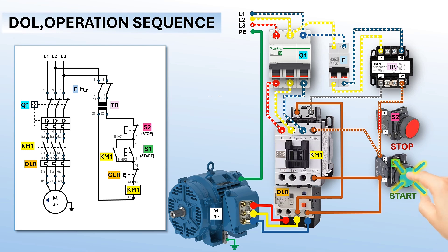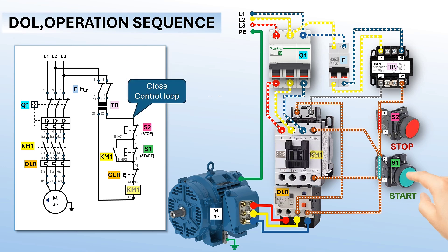To run the motor, press the start push button. Once the push button is pressed, the NO contact will close. Voltage at terminal 3 will directly pass terminal 4, then to overload relay terminal 96, and into terminal 14 of the auxiliary contact. From the overload relay NC contact terminals 95 and 96, the voltage will pass and reach terminal A1 of the contactor coil. When the closed loop in the control circuit is established, the magnetic coil will be energized and picked up, and all KM1 main and auxiliary NO contacts will go to the closed position.